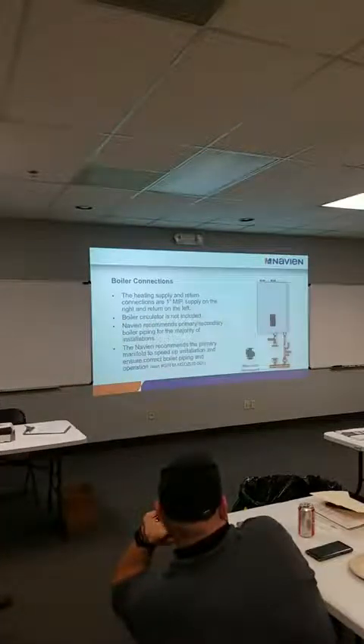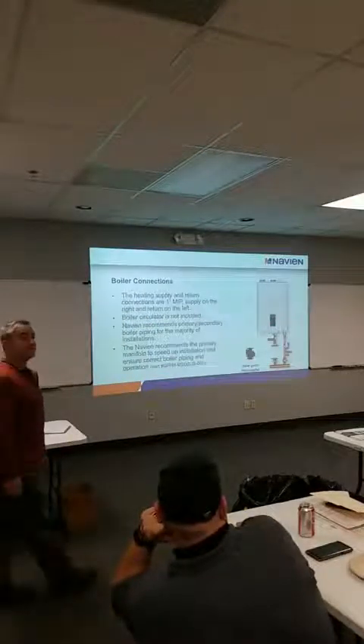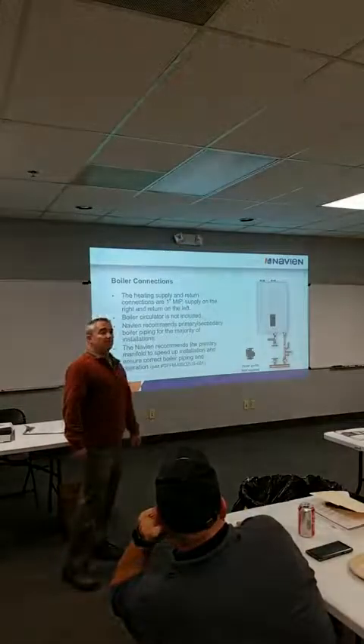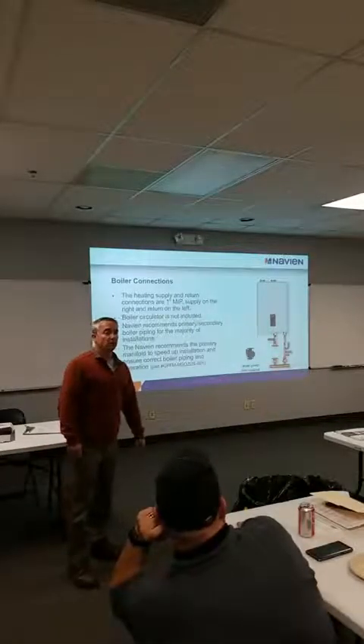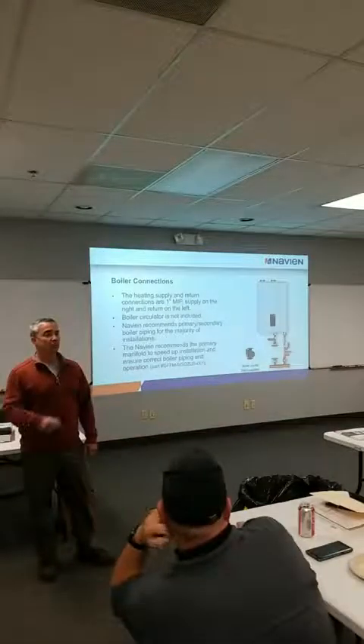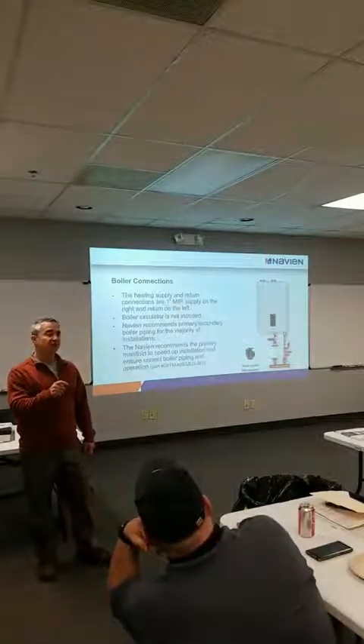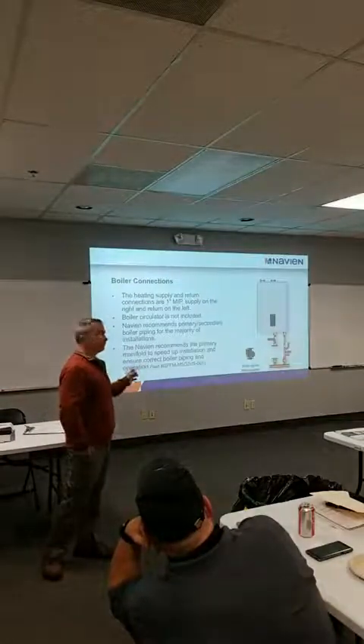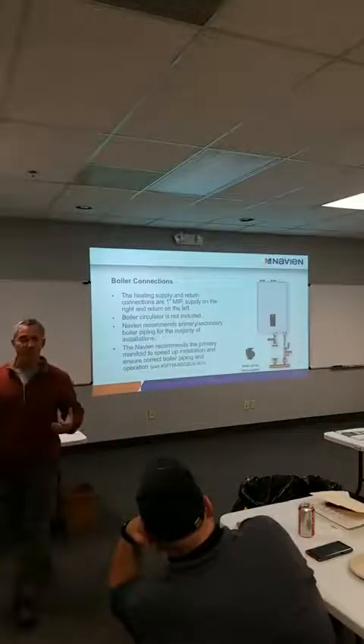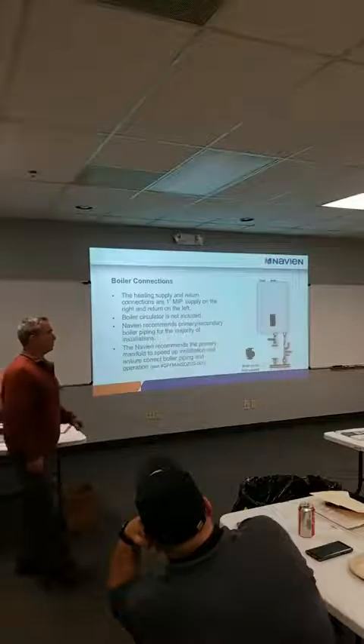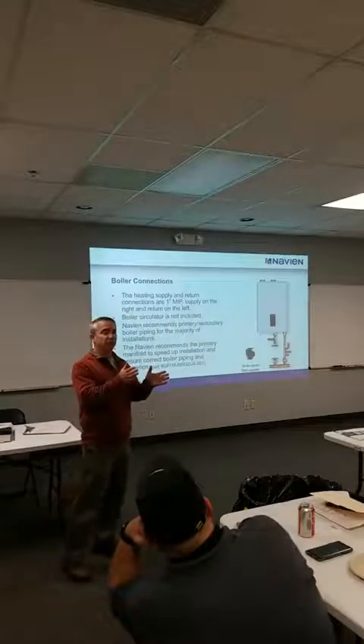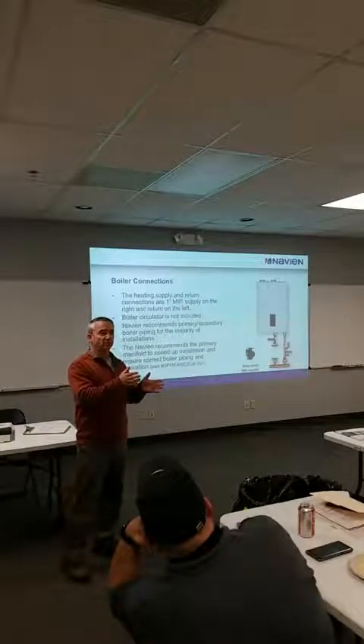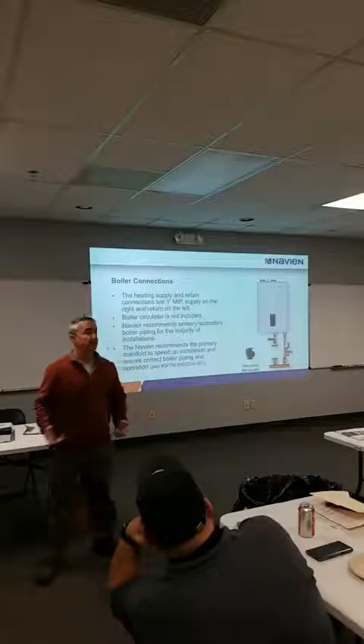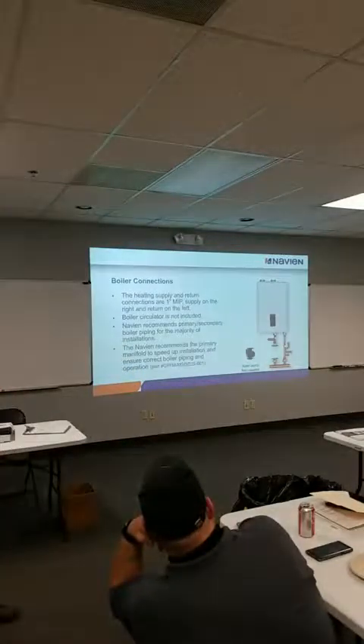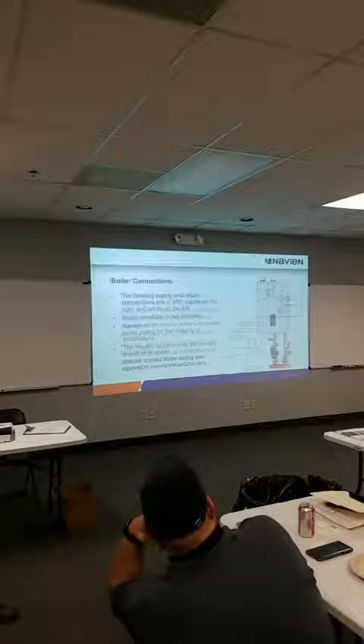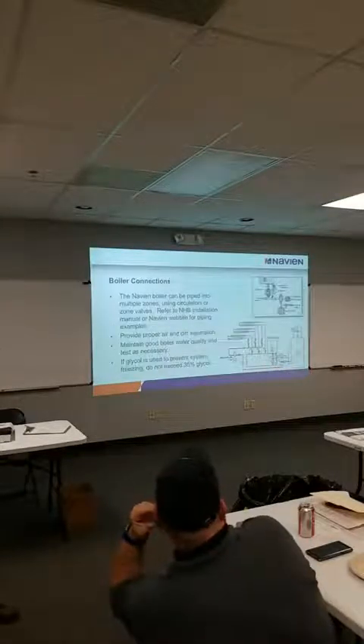Are those flanges compatible with Taco and Grundfos, or just one or the other? Grundfos, Taco, Armstrong, Wilo. And we give you a model number for each of those manufacturers. What the regular pump is? Yeah, for the pump. So we know that. I know Wilo made a couple different pumps that had a bigger flange on it, but it's basically the same part number with a different letter on it, and they didn't fit. Pretty slick now.